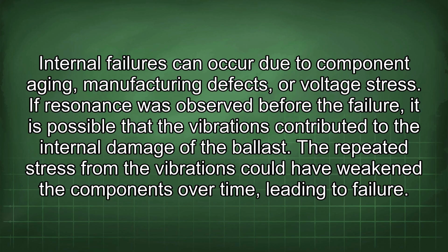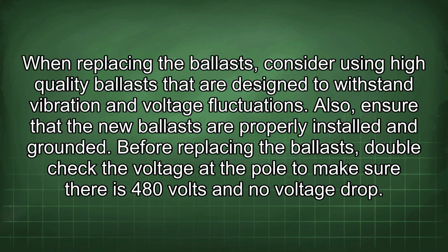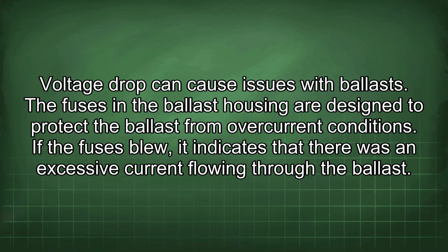If resonance was observed before the failure, it is possible that the vibrations contributed to the internal damage of the ballast. The repeated stress from the vibrations could have weakened the components over time, leading to failure. When replacing the ballast, consider using high-quality ballasts that are designed to withstand vibration and voltage fluctuations. Also, ensure that the new ballasts are properly installed and grounded. Before replacing the ballasts, double-check the voltage at the pole to make sure there is 480 volts and no voltage drop. Voltage drop can cause issues with ballasts.